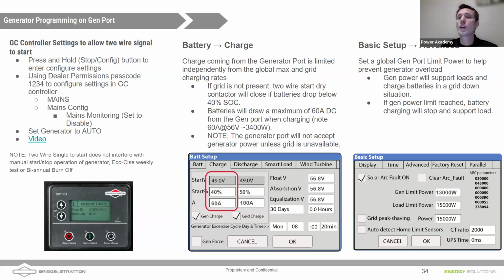Nathan, we did have a question. Okay, go ahead. What can you do if a mobile generator causes the home's LED lights to flicker and flash? That's a good question. I don't have a slide on that, but there are some settings under the grid parameters in the Sol-Ark inverter. If it's pass-through that's causing that, I'm not sure there's a lot we can do. That is coming from the generator alternator and controller itself. Perhaps buy a higher quality portable generator from Briggs and Stratton.